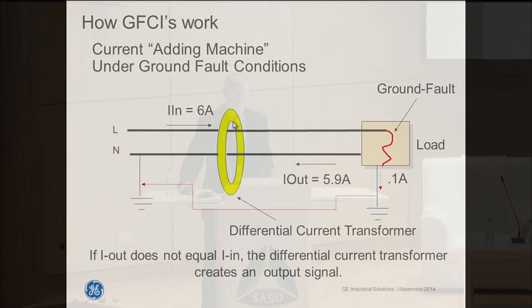So when a ground fault circuit interrupter senses a problem with a circuit, some of the current that's flowing to a load will be redirected to ground or to earth. And so the load coming back through the return will not equal. In this example, we've got 6 amps flowing out to a load and 5.9 amps flowing back, losing 0.1 amps or 100 milliamps. The differential current transformer senses an imbalance, and sends a signal electronically to the trip mechanism of the device and causes it to trip. There are also very specific guidelines for the timing of the trip that's required as well.